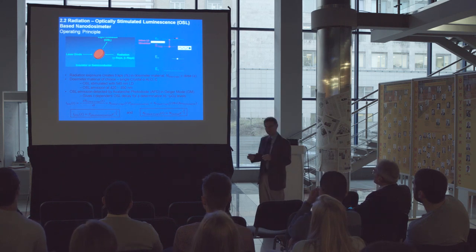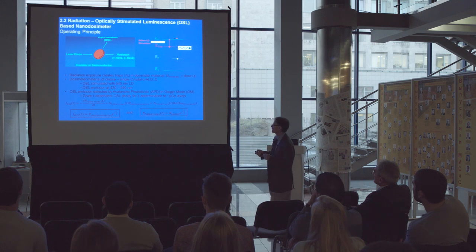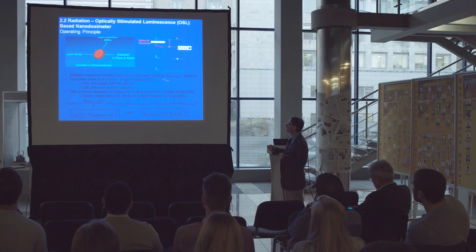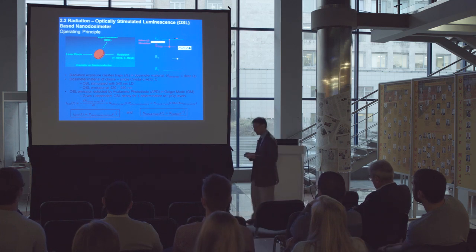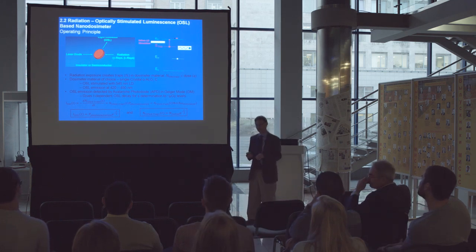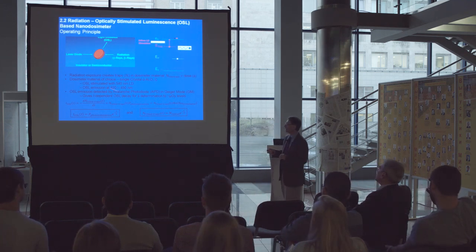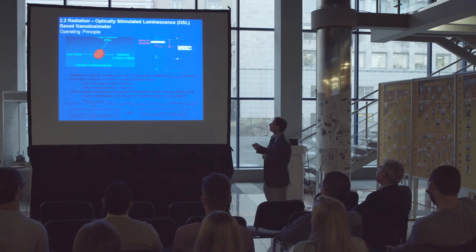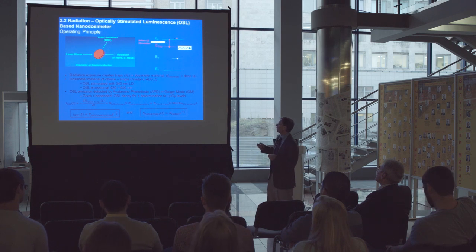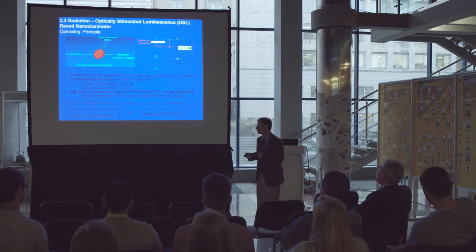So anyway, I'll explain how we went about building these dosimeters. The idea of dosimeter material is, again, very much this idea of particular electronic states and taking advantage of them. In materials such as carbon-doped alumina, which is this thing over here, radiation will be absorbed and will create effectively trap levels. These are the trap levels here. And the number density of traps is in proportion to the dose of the radiation.